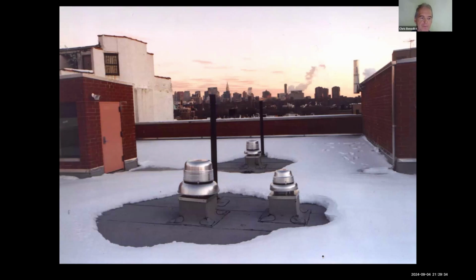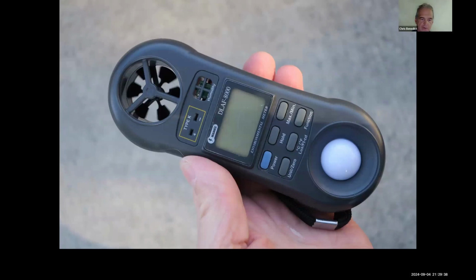So to stop this waste of just dumping heated and cooled air outdoors, here's how you measure air. They sell this little thing with a propeller and it measures it. It looks good. They're not expensive. They don't work well because you hold this in front of a grill. You don't know that the air changes all across the grill. It's mostly theater. Testing and balancing, people love them.